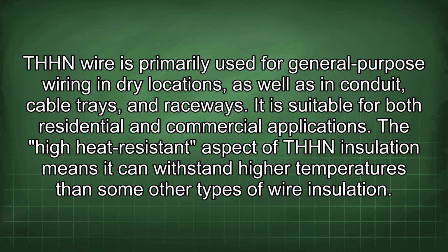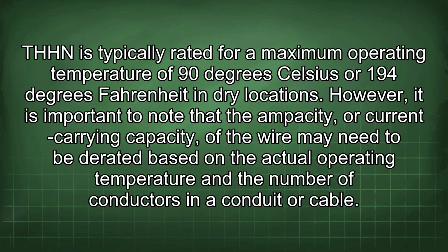THHN wire is primarily used for general-purpose wiring in dry locations, as well as in conduit, cable trays, and raceways. It is suitable for both residential and commercial applications. The high heat-resistant aspect of THHN insulation means it can withstand higher temperatures than some other types of wire insulation. THHN is typically rated for a maximum operating temperature of 90 degrees Celsius or 194 degrees Fahrenheit in dry locations. However, it is important to note that the ampacity or current carrying capacity of the wire may need to be derated based on the actual operating temperature and the number of conductors in a conduit or cable.